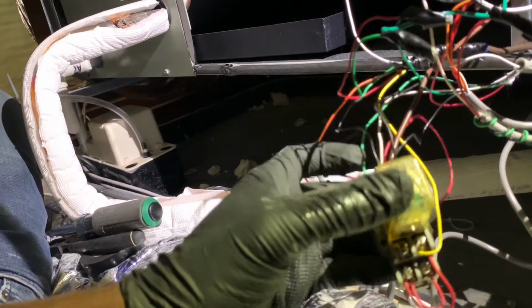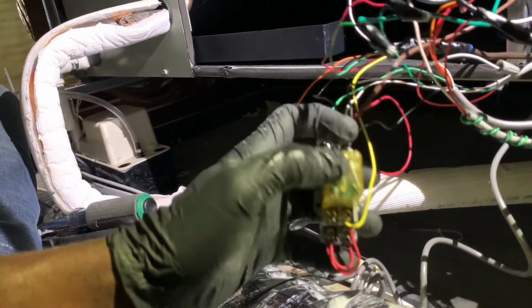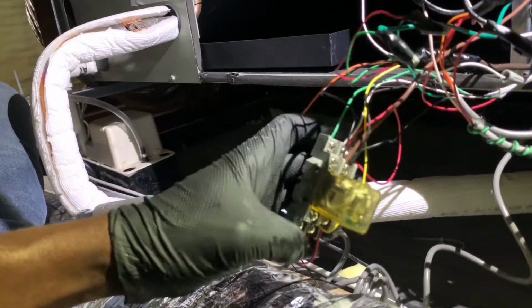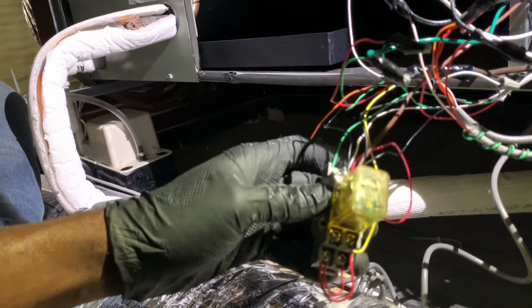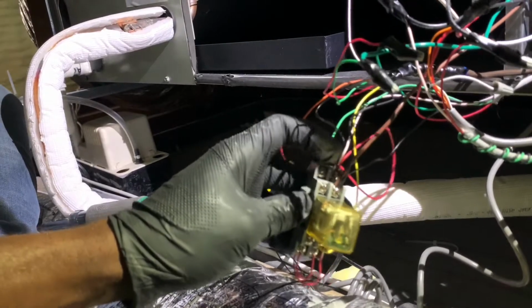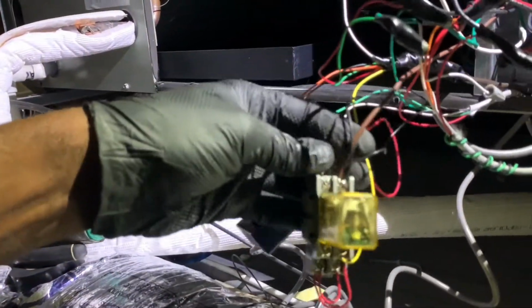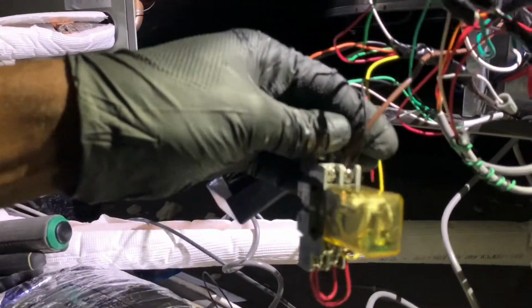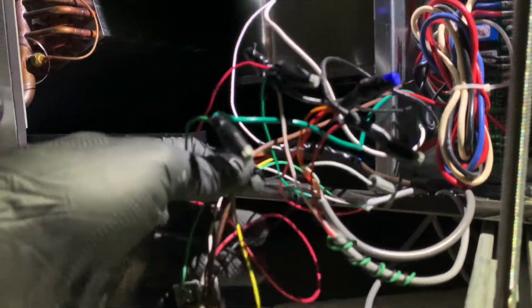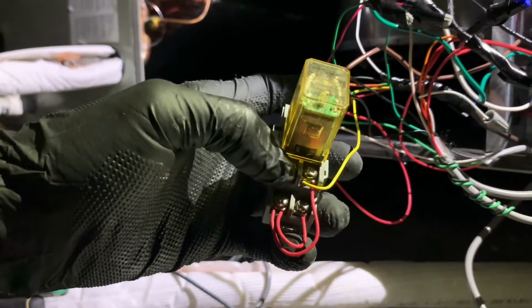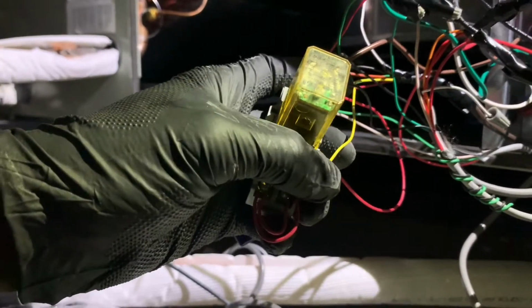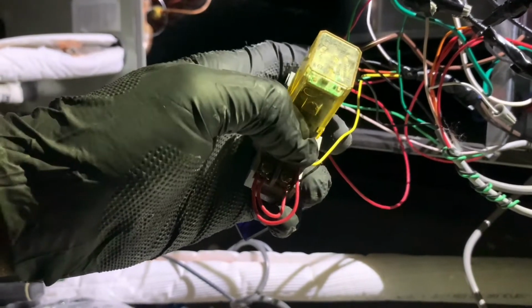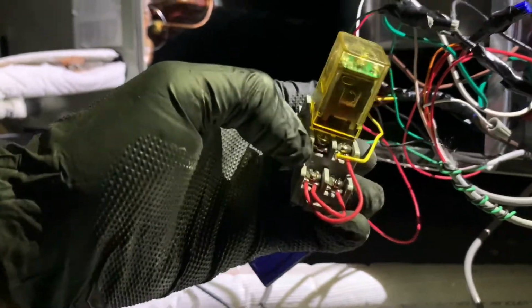Okay, and that's pretty much it, as a matter of fact. This yellow wire. I'm going to have to put these wires right here. As I'm doing this video, I found that there's a slight mistake in my configuration, because this is the common. This is the common from the unit, the brown wire. There's a brown wire right here. So I'm supposed to take this common and put it over here on the other side of this relay. This is a coil. These two terminals right here are a coil. So this right here is going to be activated from the cooling signal, yellow wire. That's one side of the coil, and over here is the other side of the coil.